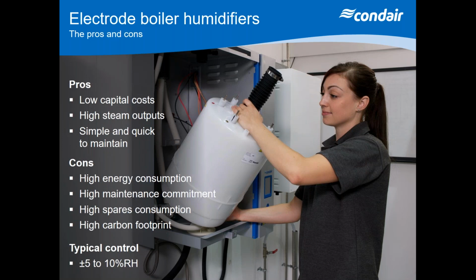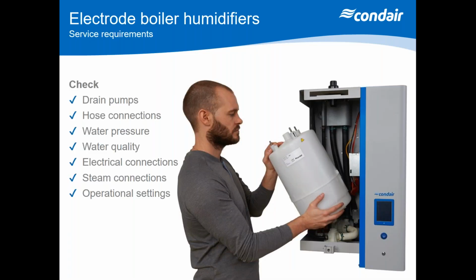Now, because we're boiling water, there's going to be a high energy consumption. If you're looking at a 100 kilogram an hour system, you're looking at 75 kilowatts of electrical energy to boil 100 litres of water an hour. So that's quite a high energy consumption. If your maintenance commitment is high, you could be looking, as I say, at 2 or 3 maintenances a year. And what you should be doing with the maintenance is taking these cylinders out, inspecting the plates or the electrodes to make sure they're intact, or if they're heavily scaled, then you should replace them.